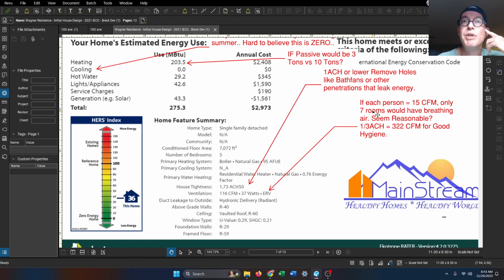So if it's 15 CFM per person at our current rate, we're only ventilating about 7 people—7 rooms that are going to have breathing air. Which means at Christmas time, etc., with 2 people in a room, you're going to be breathing each other's air.